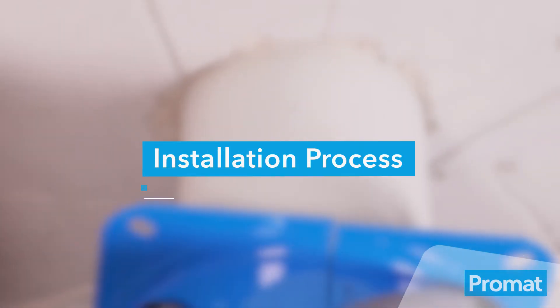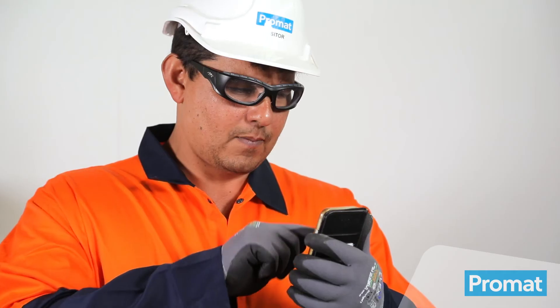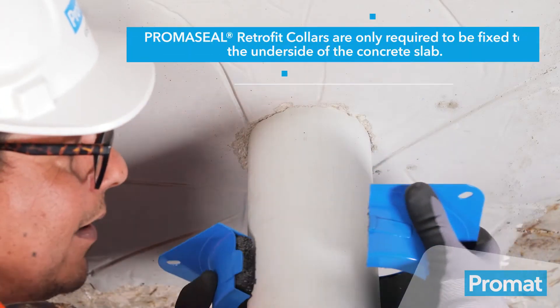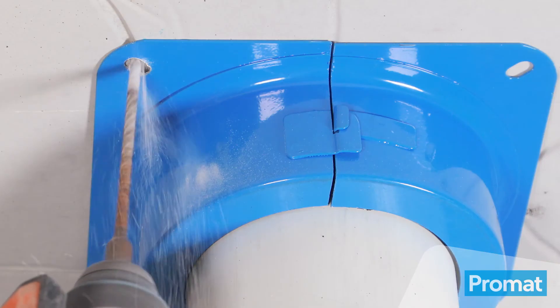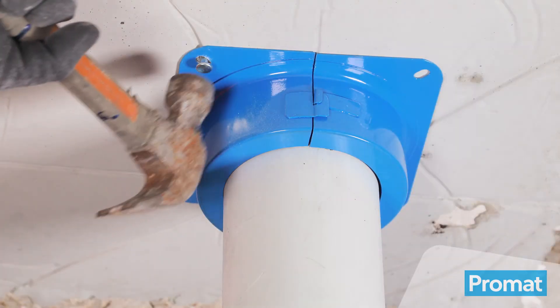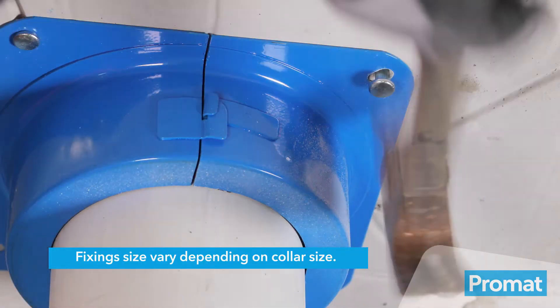To install the Promaseal Retrofit Collar into a floor slab, measure the outside diameter of the plastic pipe. Use the Promat Collar Selector app to ensure your application is approved. Unclip the collar and place it around the pipe. Re-clip the collar and push it tight into the substrate. To fasten the Promaseal Retrofit Collar, pre-drill to the required depth — about 20 mm for this application. Insert steel anchors into the hole and hammer into place.